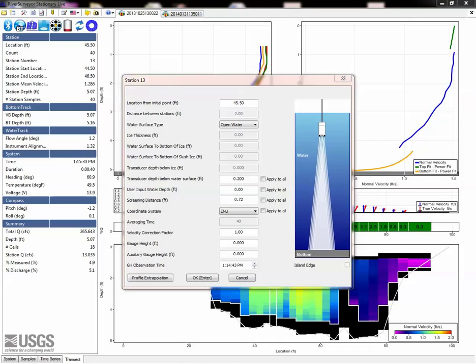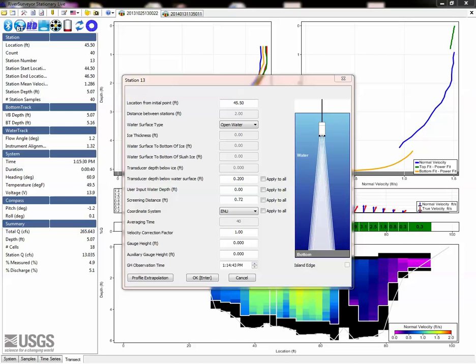Before reviewing extrapolation in RSSL, be sure the screening distance is set appropriately in the software, as this will cause data near the surface to be removed and might change your evaluation of the methods used. As a reminder, the screening distance is set to 0.52 plus the transducer depth for open water measurements.